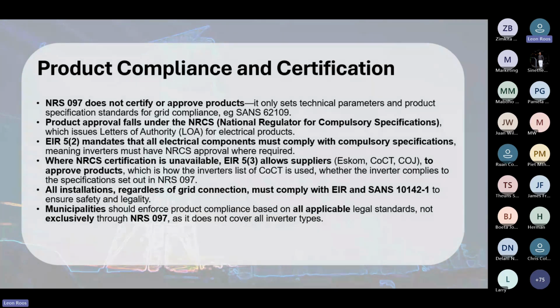But apart from that, the entire installation still needs to comply with the Electrical Installation Regulations and SANS 10142, whether it is a grid-tied connection or other type of connection. So the municipalities should enforce product compliance based on all the applicable legal standards, not exclusively NRS 097, as 097 does not cover all the inverter types.